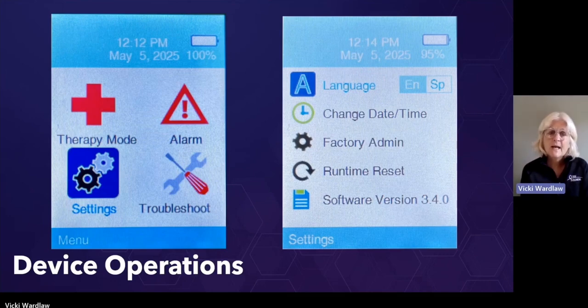Factory admin, that black gear, just keep in mind that we do have the ability to tailor this device to a particular situation with a patient. Typically, if we use this, it would be for a patient that maybe has a delay from the positioning from point A to point B, bed to chair, there's a Hoyer lift, they're lying on their port pad, and the blockage alarm sounds. If we need to give the device a little more time, or give it a little more information so it doesn't automatically think there's a blockage, we can change the thresholds in the device itself. It does not change the therapy that the patient is receiving. It just gives the device a little more time to recognize what is happening with that particular patient. And your clinical support team can help you with that.